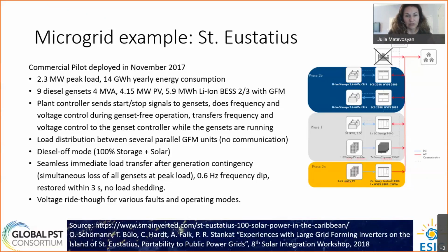So the overall plant controller sends start and stop signals to the genset. It does frequency and voltage control during genset free operation, so when the genset is not online. And then once the genset is online, it transfers frequency and voltage control to the genset controller. Load distribution is done on several parallel grid forming units. So there are 2 grid forming inverters. And there is no external communication required. They tested the project in diesel off mode in a testing stage, and now diesel is being turned off in the middle of the day when it's sunny and there is sufficient storage.